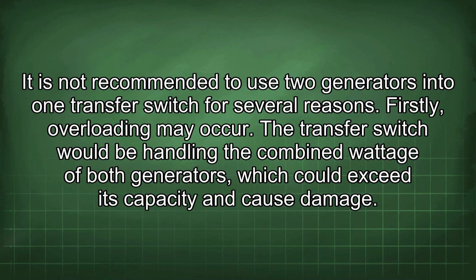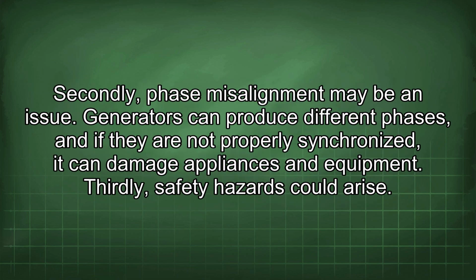It is not recommended to use two generators into one transfer switch for several reasons. Firstly, overloading may occur. The transfer switch would be handling the combined wattage of both generators, which could exceed its capacity and cause damage. Secondly, phase misalignment may be an issue. Generators can produce different phases, and if they are not properly synchronized, it can damage appliances and equipment.